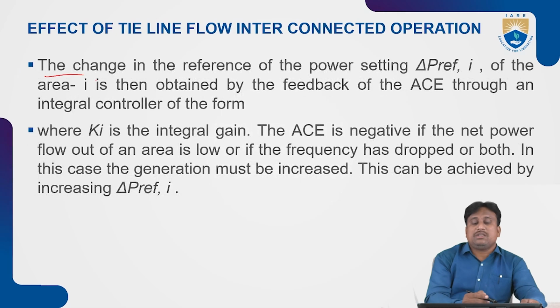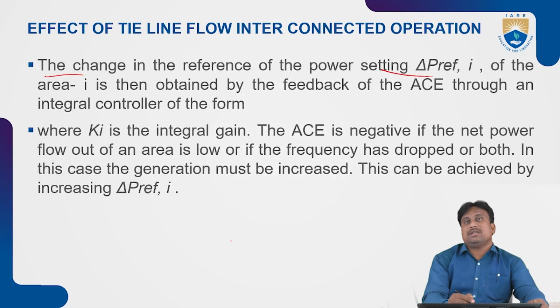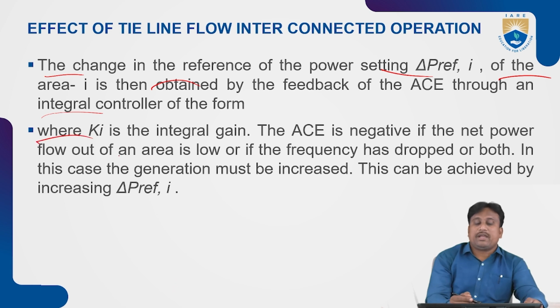So that change in the reference of the power setting, delta P reference of area i, is then obtained by the feedback of the area controller. That should be through the integral control of the form, where Ki is the integral gain and the area control error is negative.